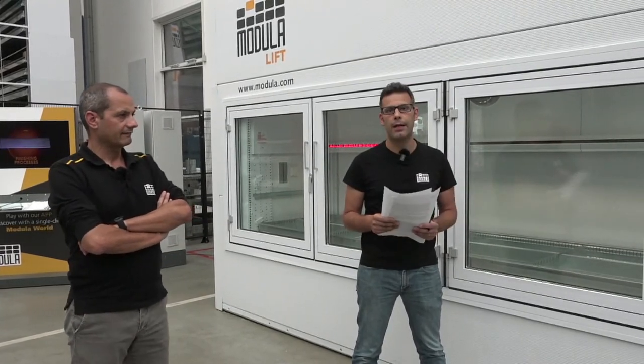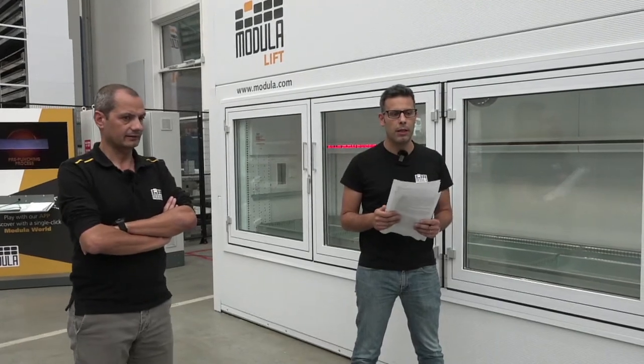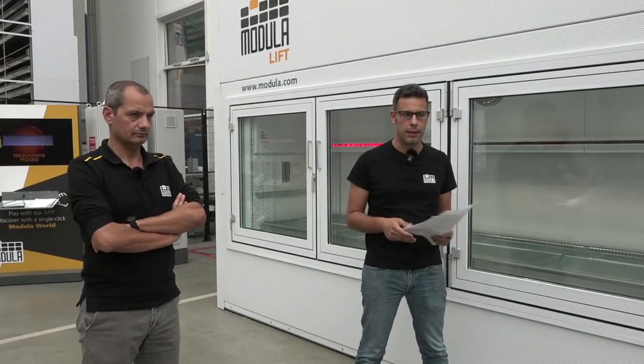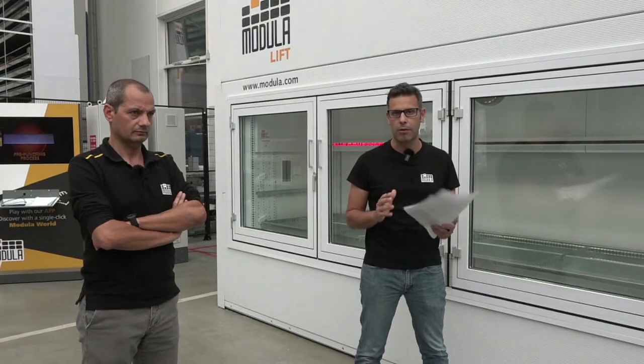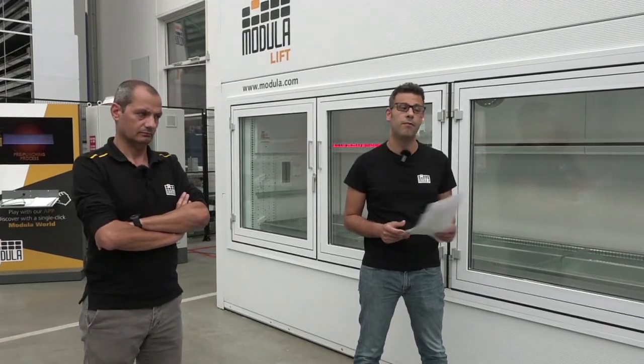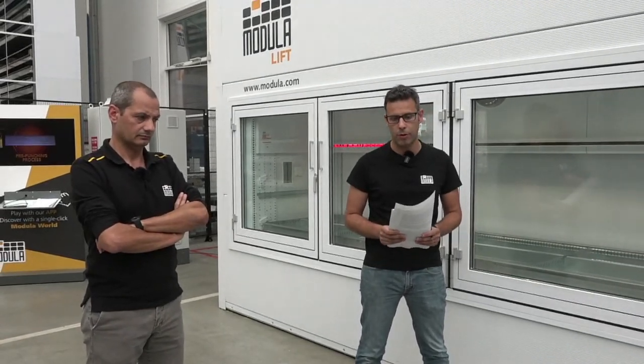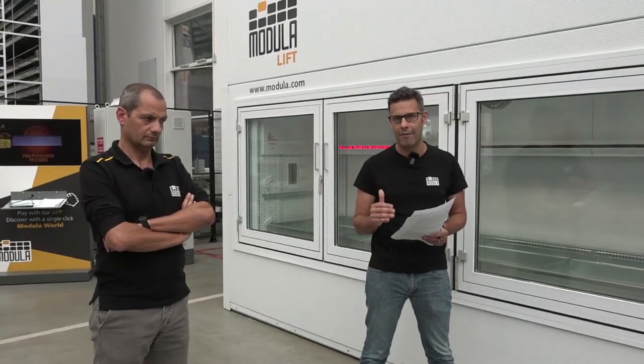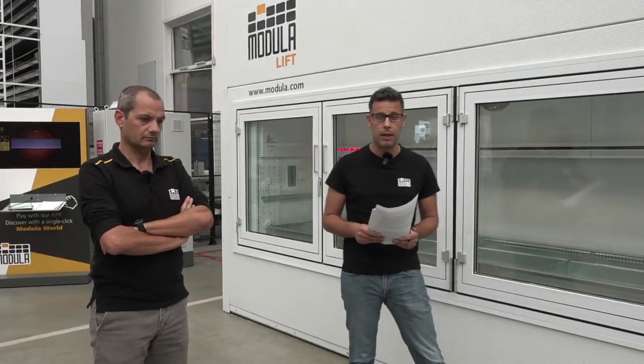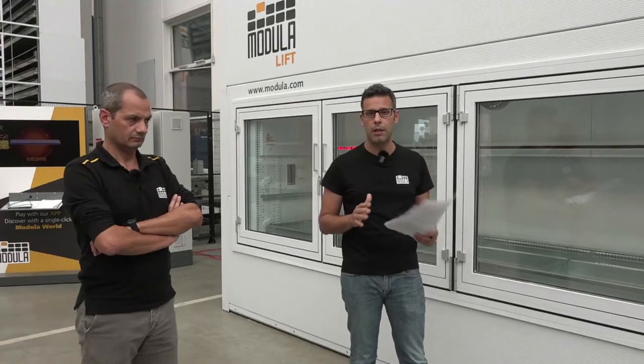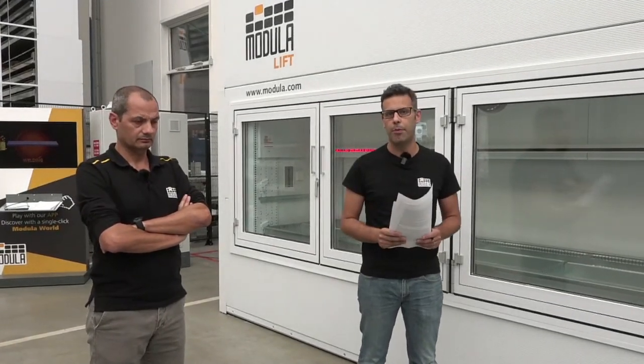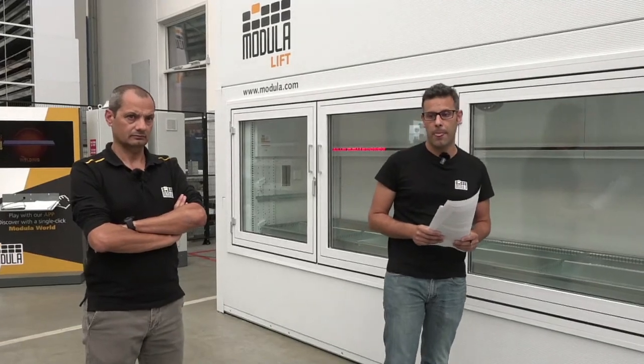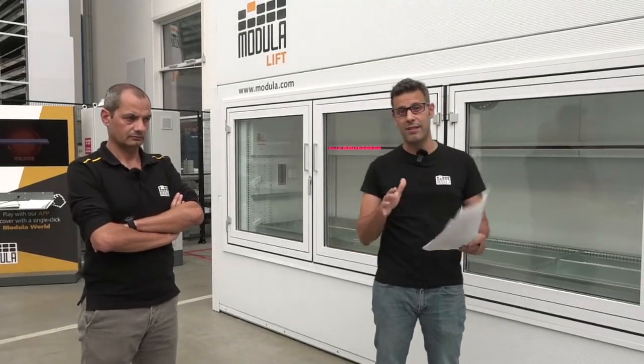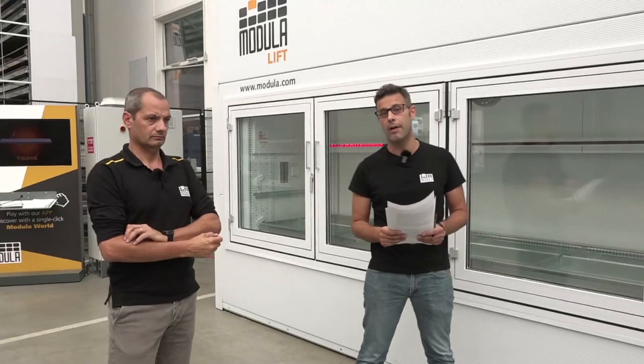Using the dehumidifier, we can address customer applications, for example, in the electronics and semiconductor industry. It's very important in these applications to reach a very low level of relative humidity, and with our system it's possible to reach a relative humidity around 5% at a temperature of 25 degrees, which is very low.